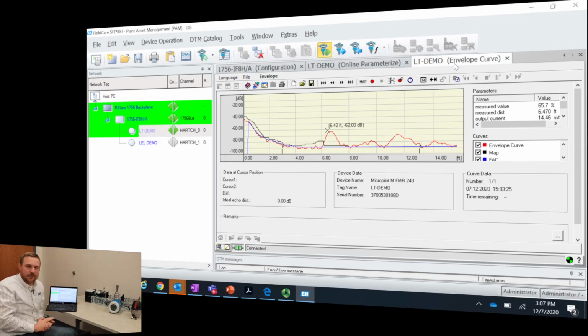False echoes can be caused from any number of sources. Sometimes it's a level switch sticking in the top of the tank creating a small echo. Sometimes it's maybe some buildup on the nozzle that the radar level transmitter is installed in, and we just have to tell the radar, ignore that, that's not the right level, look further, go look further down in the vessel to actually track the proper reading. And that's what the black line allows us to do.